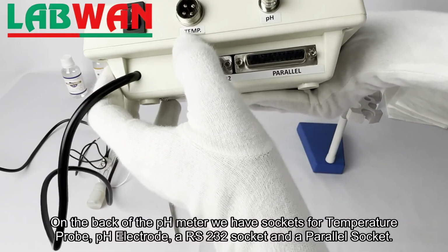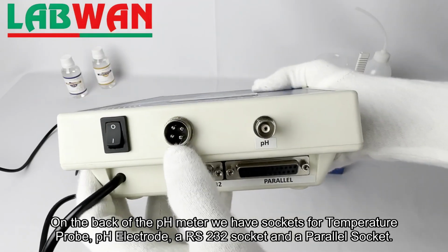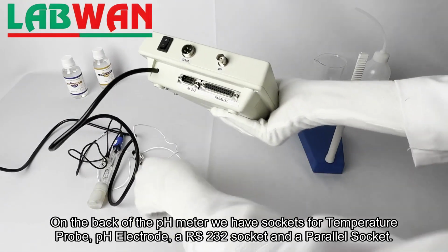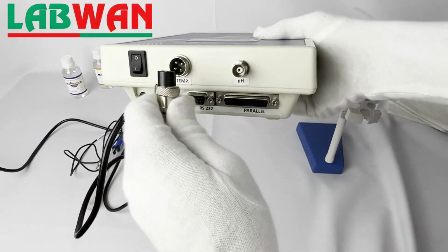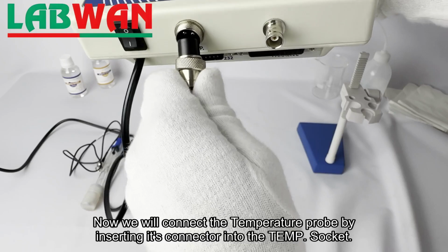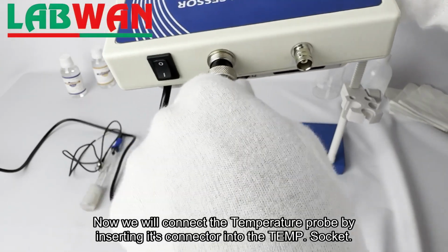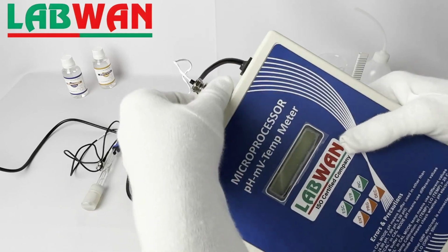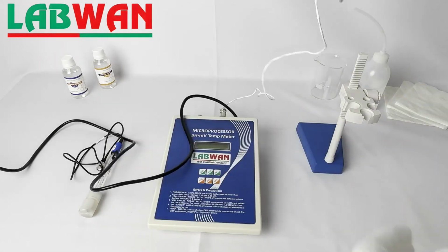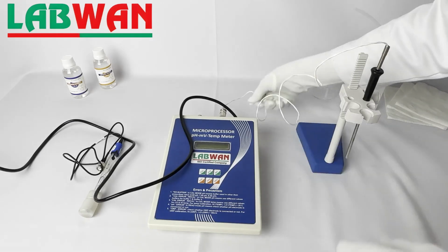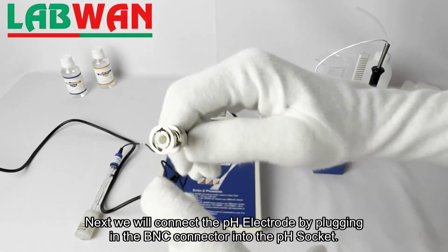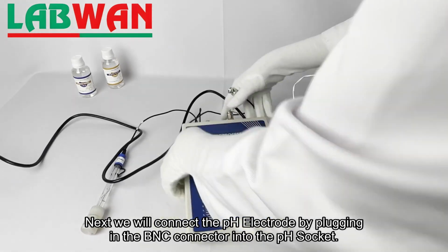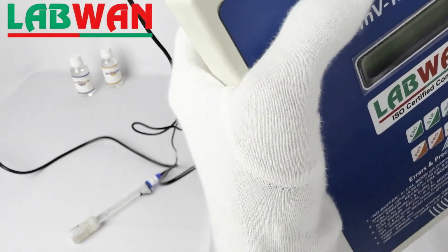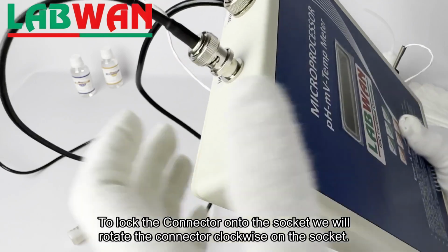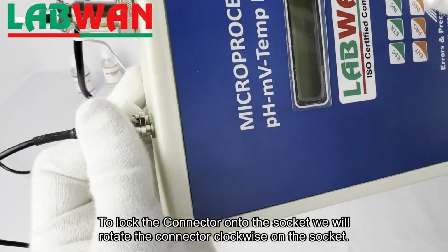On the back of the pH meter we have sockets for temperature probe, pH electrode, a RS232 socket and a parallel socket. Now we will connect the temperature probe by inserting its connector into the temp socket. Next we will connect the pH electrode by plugging in the BNC connector into the pH socket. To lock the connector onto the socket we will rotate the connector clockwise on the socket.